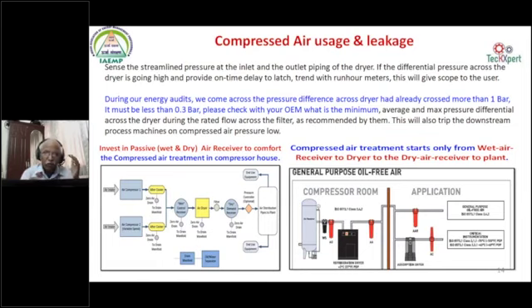Then the air is brought to a lower temperature. That is why we maintain the dew point. Once it is refrigerated, automatically whatever water vapor is there in the air is totally removed. If you look into these 3 aspects of water removal in the compressor house, this will definitely improve the pneumatic health of the industry.